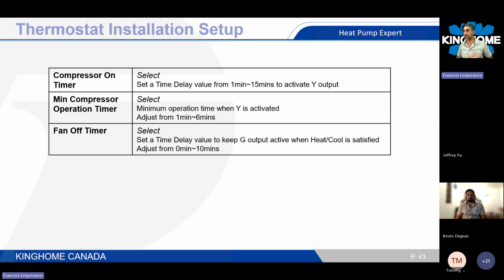Compressor on timer is a time delay value from 1 to 15 minutes to power on the Y terminal from the thermostat. So basically, you can add a time delay inside the thermostat if needed, from 1 minute minimum. Minimum compressor operation timer is a different operation. It's meant to be that whenever Y is active, it will stay active for 1 to 6 minutes. That is just to make sure the compressor gets enough oil moving in the moving parts, so lubrication goes well, and also to avoid short cycling as well. So the system will run for a minimum of 1 minute whenever it's powered.